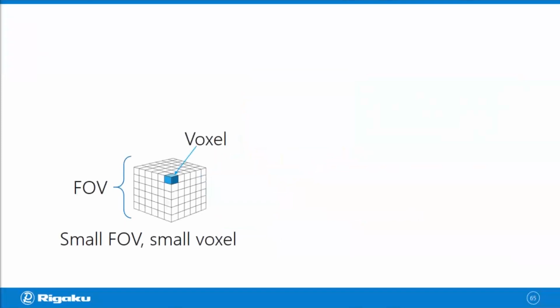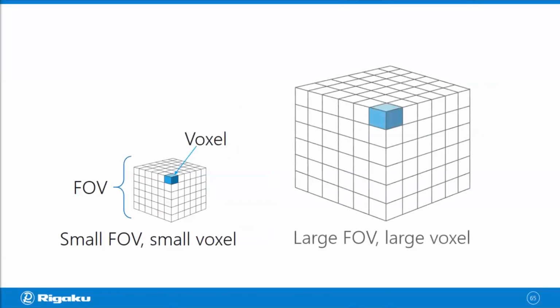And when your FOV is small, generally speaking, your voxel size is small as well. That means you have high resolution. When the FOV becomes large, your voxel size becomes large as well, meaning you have to compromise on the resolution. Sometimes people say, well, I want to scan a large FOV, but I do not want to compromise on the resolution. Unfortunately, it doesn't work that way, and I'm going to explain why.